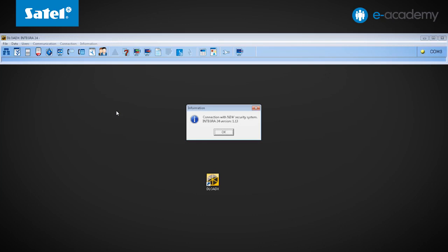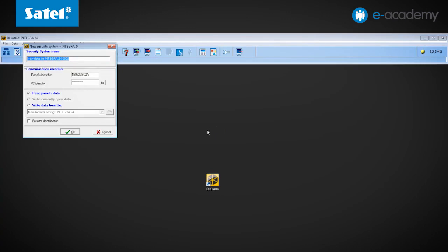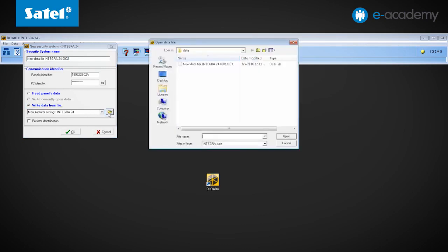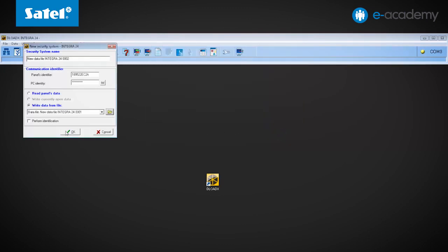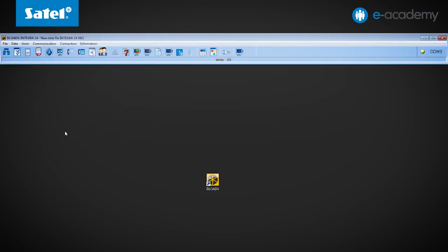The readiness for connection is reported in the program by the 'Connected with new alarm system' message. Confirming with the OK button will display the new alarm system tab. In this tab, select the Save data option and click the folder icon. As a result, the Open data file tab is displayed, where you should select the name of the file to be saved to the control panel. Once confirmed, the file name will be displayed in the dialog box. Then click the OK button again.